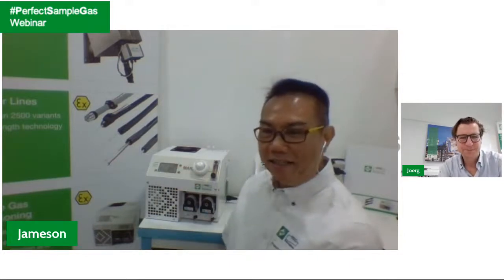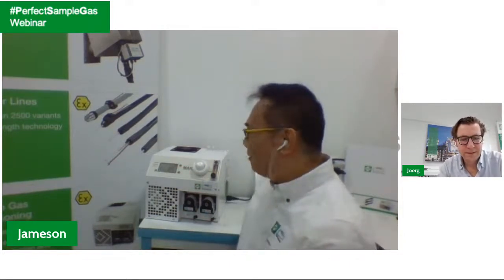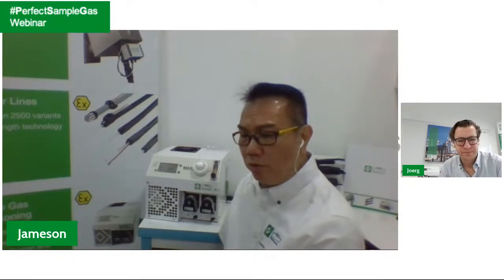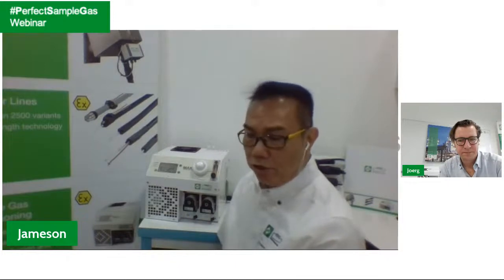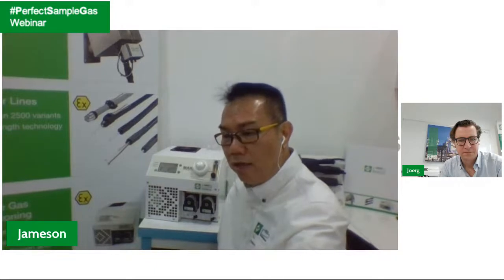Yeah. Let me take over from here for a short while. I would also like to take this chance to answer a couple of questions online now. From Vincent Earn: I agree that the hot wet is used in the incinerator. Absolutely. And then from Pabio, about the H2 in the airstream. Normally, it is really an application. We do not say that we need a gas cooler or not. Normally, not. As for H2, we do not use IR. We use thermal conductivity to measure hydrogen.